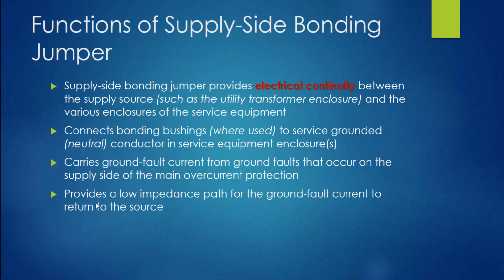Okay, and it provides a low impedance path for ground fault current to return to the source. Again, we're going to try to give any fuse that might be on the primary side of that utility's transformer the chance to possibly function. Okay, we can't guarantee it. Again, as an electrician, I deal at the service point into the premises. I'm dealing with premises wiring, not utility aspects. So we're going to give it a fighting chance, but we need to tie all those things together at the service equipment, meter enclosures, raceways, all of those locations that contain service conductors within them. We're going to tie them all together, and we're going to cover that.